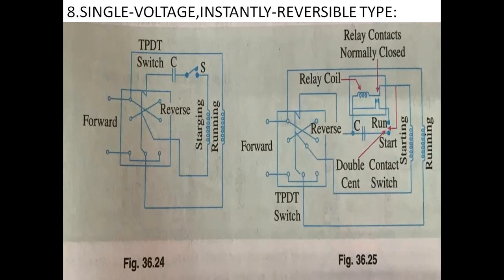For some applications, we need instant reversal while the motor is operating at full speed. A relay is fitted in the circuit which short-circuits the centrifugal switch and connects the starting winding in the circuit in the reversal position. By using the relay, if we want to instantly change the direction of the motor, we short-circuit the centrifugal switch and connect the starting winding in reverse direction. If we close or open the relay, the direction will be changed.